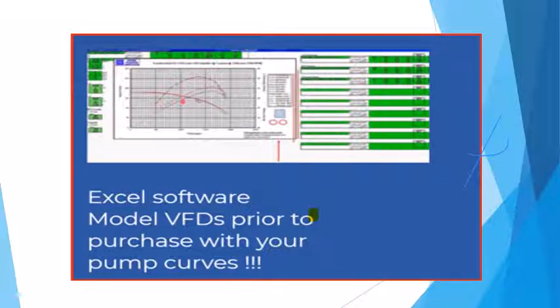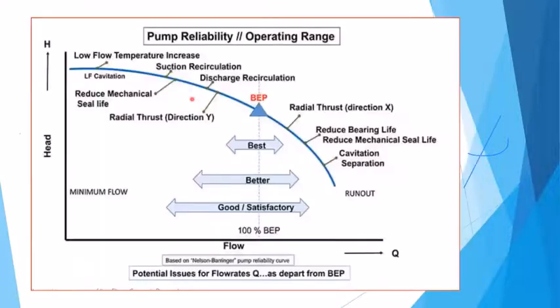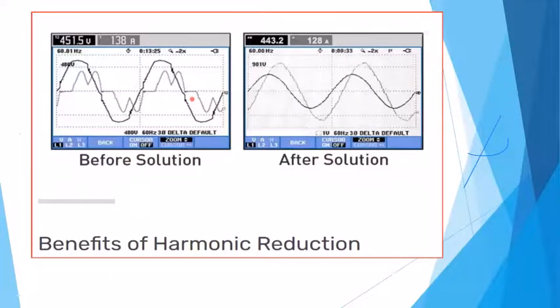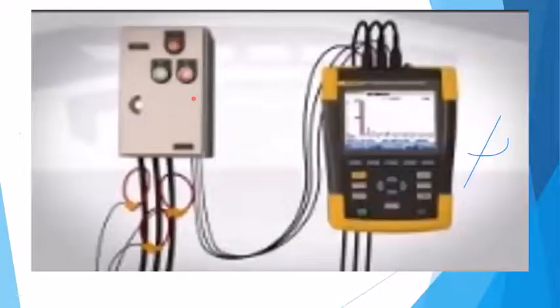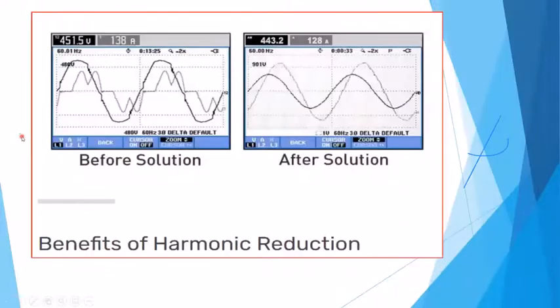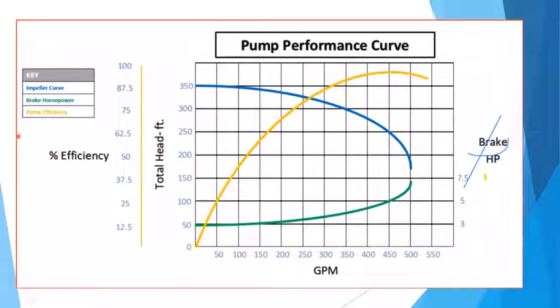So if I want to produce 1,000 gallons a minute for a certain period of time, creating a certain number of acre-feet of water in irrigation, at 1800 RPM, yes, it may be pulling more power for that period of time, but it's getting the work done faster. So the issues of these added losses in the VFD control world have to be considered. Plus, the longevity: how long is that thing going to last?